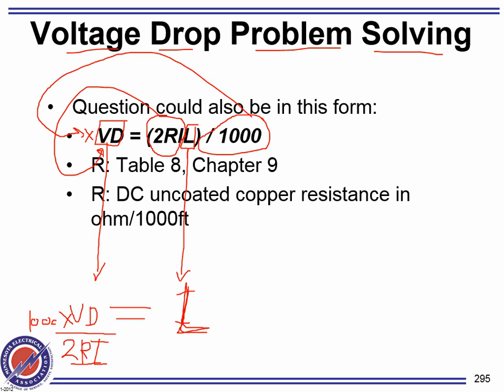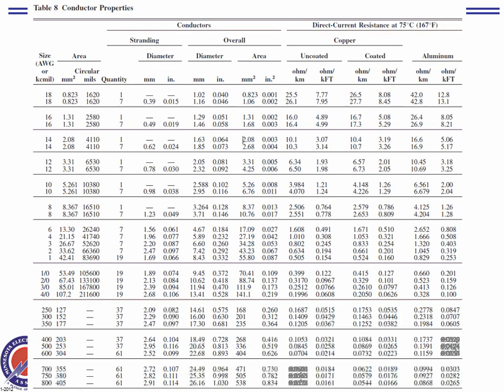So, okay. So R, let's go highlight R. This is the table that you guys, this is chapter 9, table 8. This is where the size of the wire is. This is the area in circular mil. Make sure you guys highlight it. Let's take an example. Number 12, can you guys see number 12? If it says the quantity, number 1, this means it's solid. The quantity, number 7, this means it's stranded. Everybody can see the difference between solid and stranded?